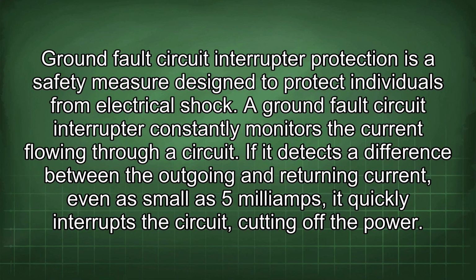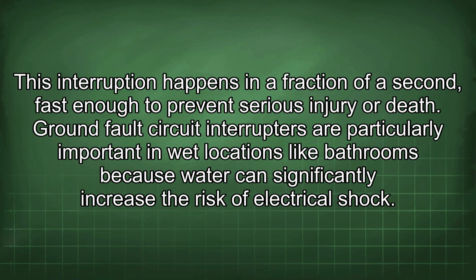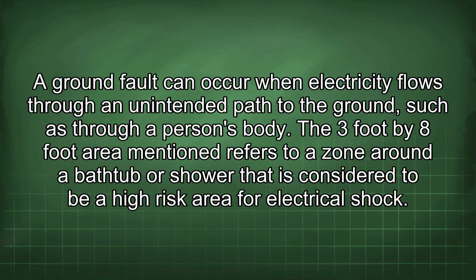Ground fault circuit interrupter protection is a safety measure designed to protect individuals from electrical shock. A ground fault circuit interrupter constantly monitors the current flowing through a circuit. If it detects a difference between the outgoing and returning current, even as small as 5 milliamps, it quickly interrupts the circuit, cutting off the power. This interruption happens in a fraction of a second, fast enough to prevent serious injury or death. Ground fault circuit interrupters are particularly important in wet locations like bathrooms because water can significantly increase the risk of electrical shock.